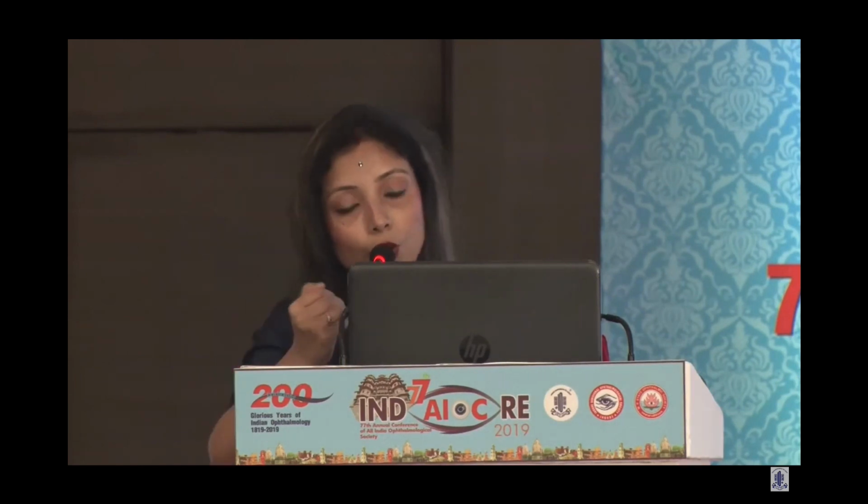disposal zone. The ventilation in an operation theatre should have a central AC, or a split AC is as good, but there is a strict no to fan usage and window AC. The water tank should be a separate one for the OT, and it should be cleaned once in a month, and that cleaning has to be maintained in a register or a logbook. The occupancy should be limited to 8 persons, and even the equipment load should be limited to 7 kilowatt.